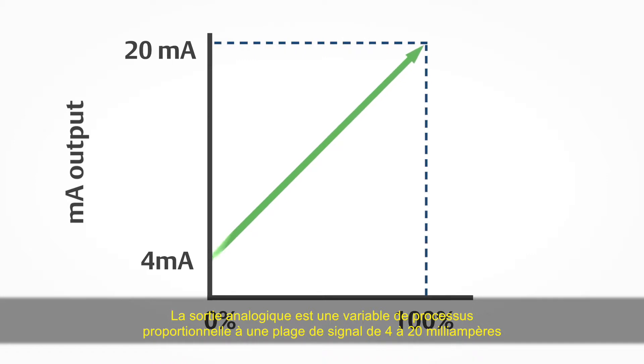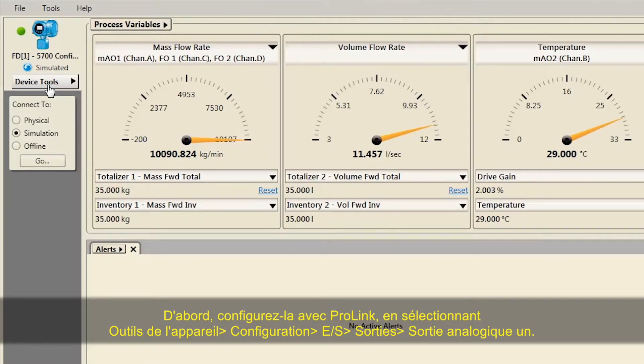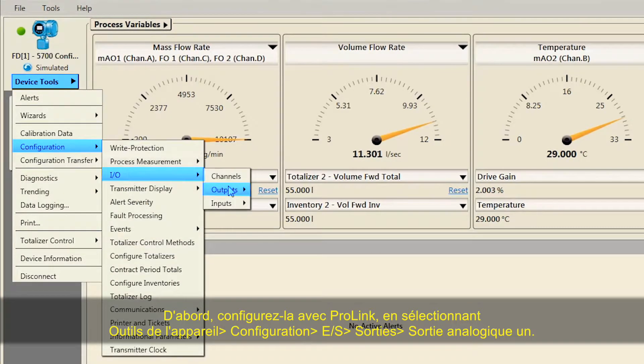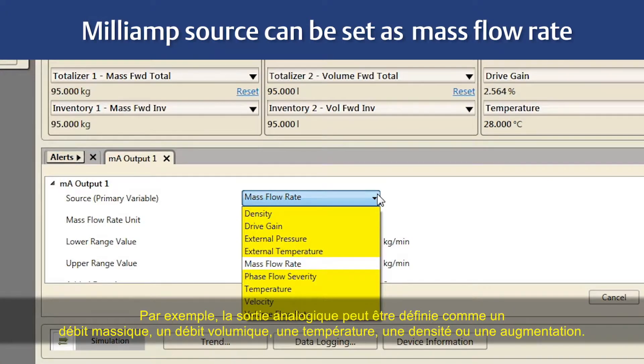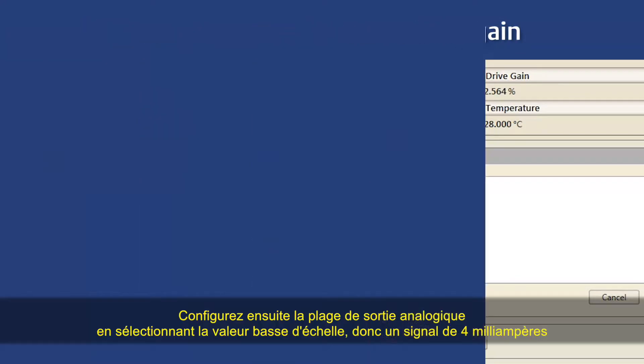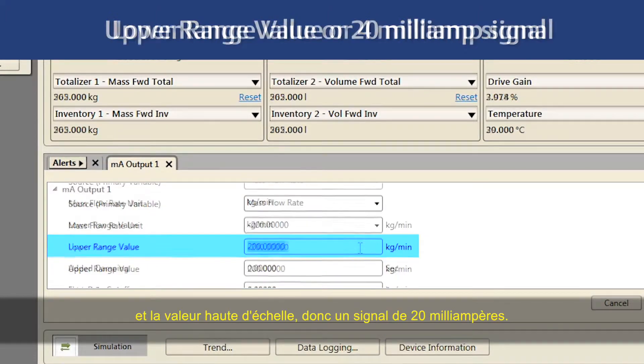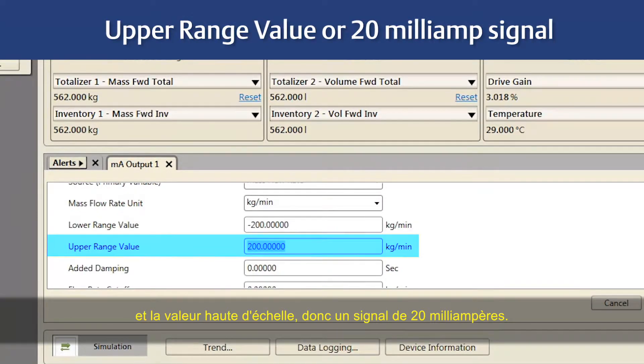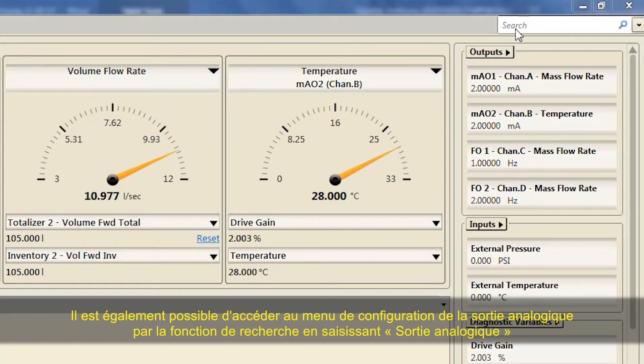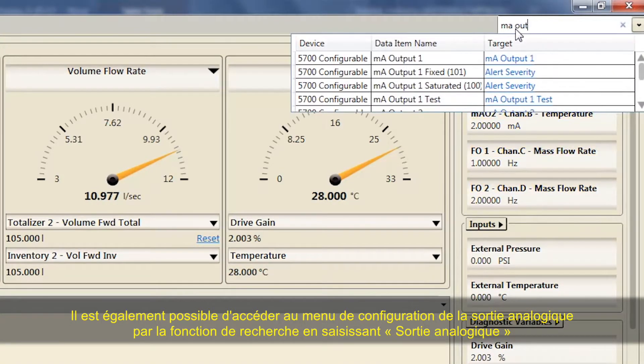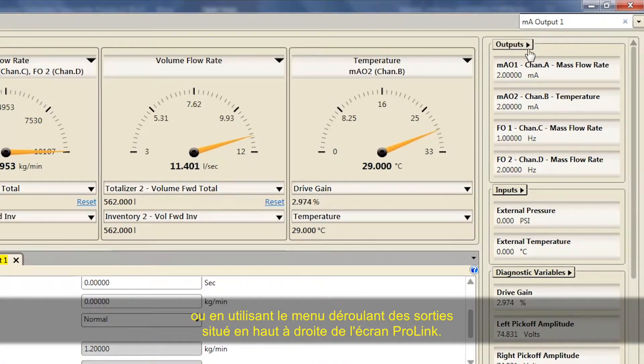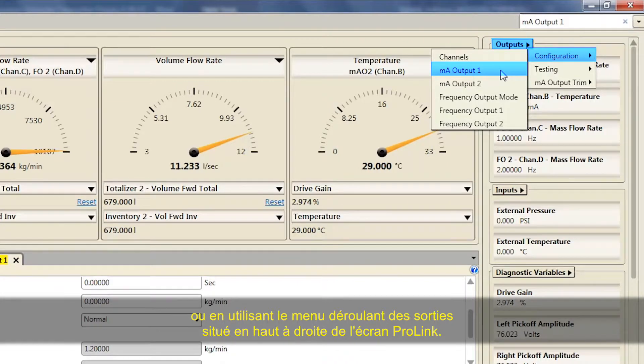The milliamp output represents a process variable in proportion to a signal range of 4 to 20 milliamps. First, configure the milliamp output using ProLink by selecting Device Tools > Configuration > I-O > Outputs > Milliamp Output 1. The milliamp source can be set as Mass Flow Rate, Volume Rate, Temperature, Density, or Drive Gain. Second, configure the range by selecting Lower Range Value (4 mA signal) and Upper Range Value (20 mA signal). The milliamp configuration menu can also be accessed via the search function by typing "MA Output" or using the Outputs pull-down menu at the top right of the ProLink screen.